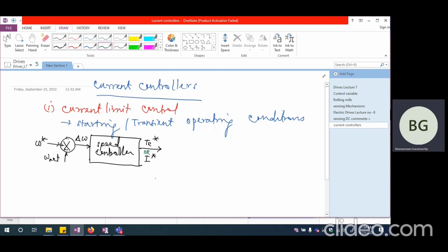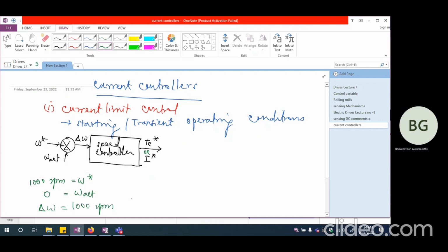So the current reference has now come up. Especially during starting, for example, maybe I want to achieve 1000 RPM speed. This is my reference speed. But I'm starting the motor drive, so the actual speed is going to be 0. So the error is going to be really, really high - this is going to be 1000 RPM. So if I say 1000 RPM is the speed I want, I am really going to require a huge amount of torque to accelerate to 1000 RPM in a very short span of time.